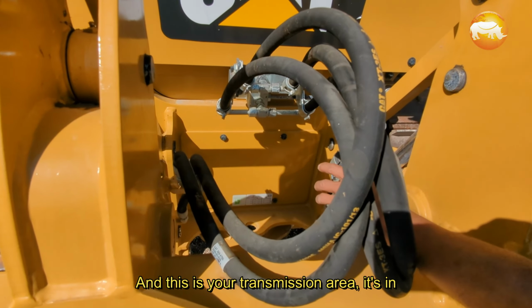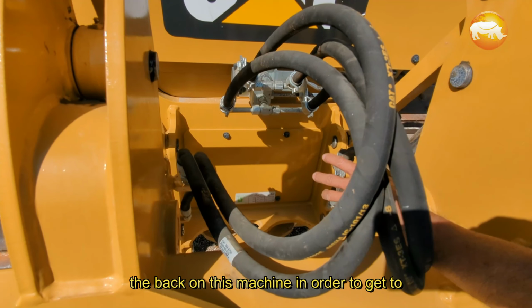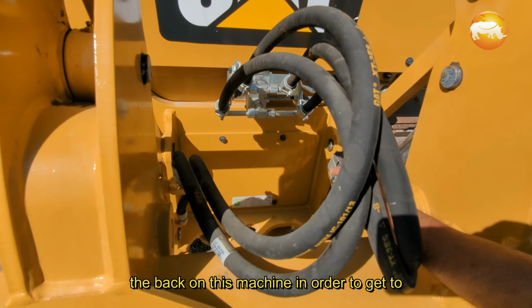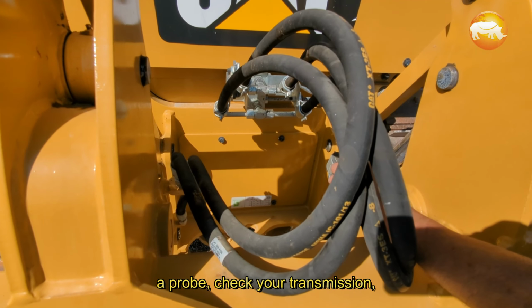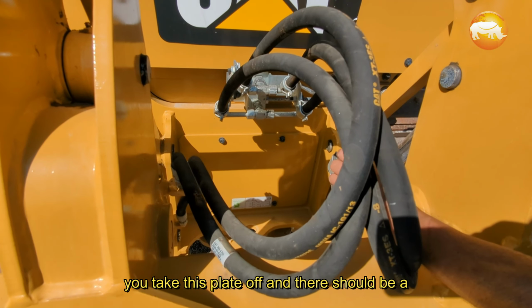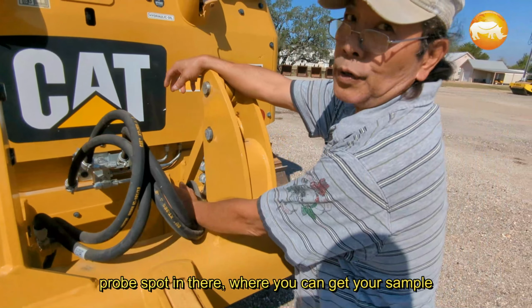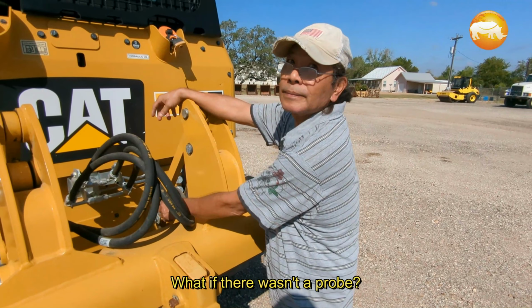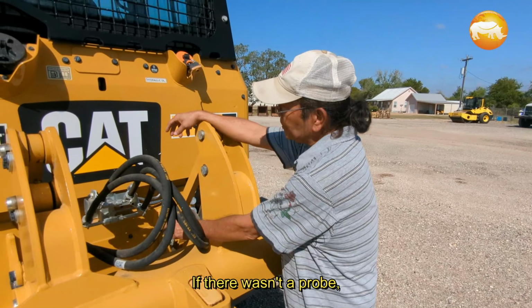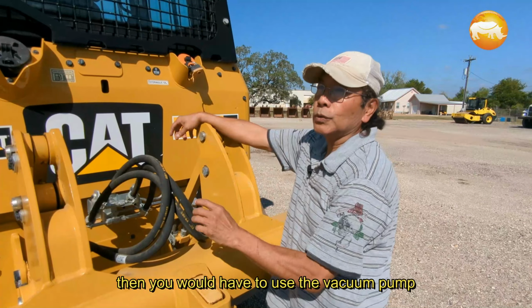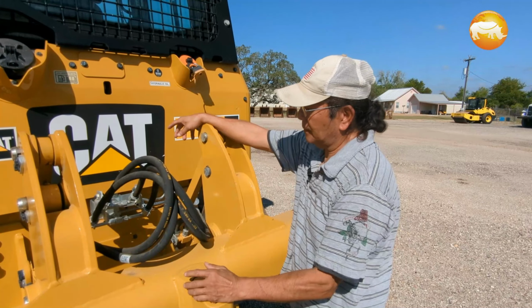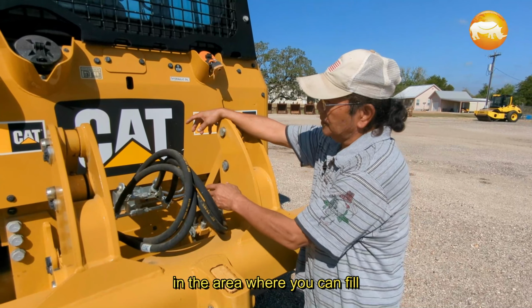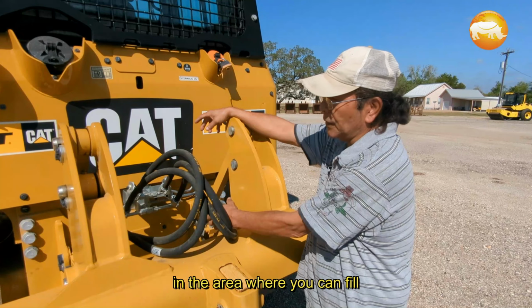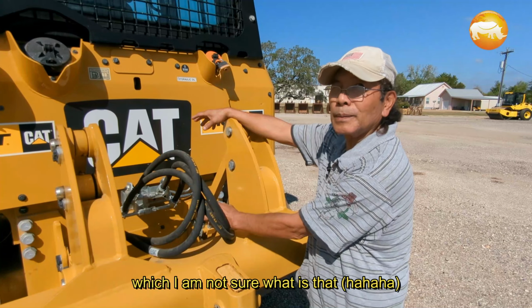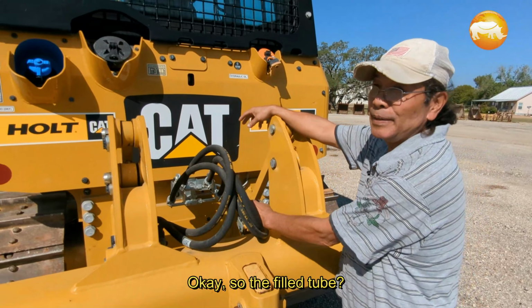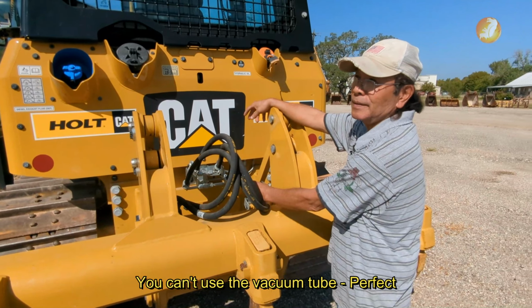And this is your transmission area. It's in the back on this machine. In order to get to your probe and check your transmission, you take this plate off, and there should be a probe spot on there where you can get your sample. What if there wasn't a probe? If there wasn't a probe, then you would have to use the vacuum one, which is the area where you fill the transmission up, which on this one I'm not sure. Gotcha. Okay. But you would go to where you fill the fill tube. The fill tube, correct.